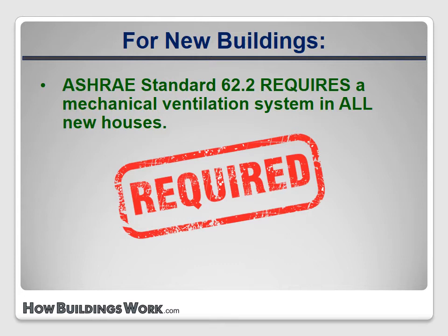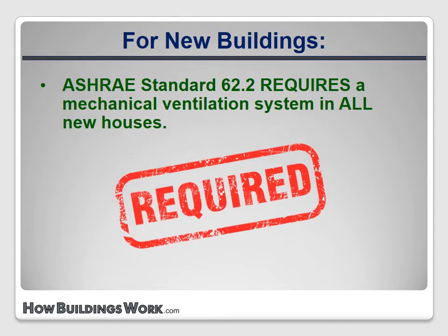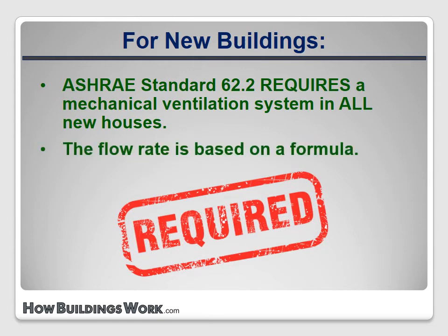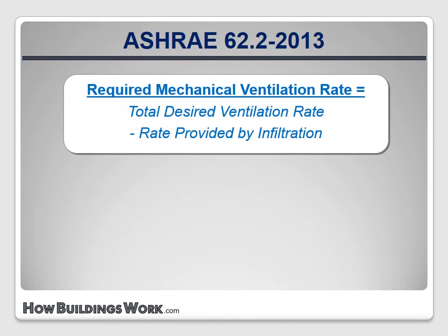But if you're participating in a program that specifies compliance with ASHRAE 62.2, like Energy Star Homes or LEED for Homes, then installing the ventilation system is required, and it must deliver a flow rate calculated based on a formula in the standard. The fan-driven ventilation rate required by ASHRAE 62.2 2013 is based on two factors: the total desired ventilation rate and the amount of that rate provided by infiltration.